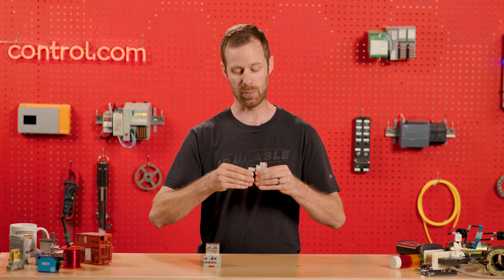So how do we fix that? We look at the device responsible for causing the spark in the first place — we might look at that large coil, or we might look at the coil of these relays. Now, in this relay, even though it's small, we can still have that problem.